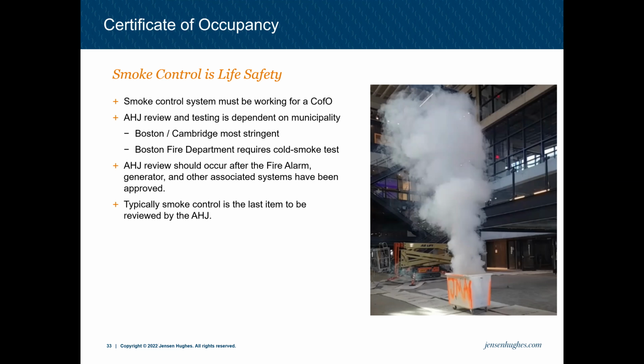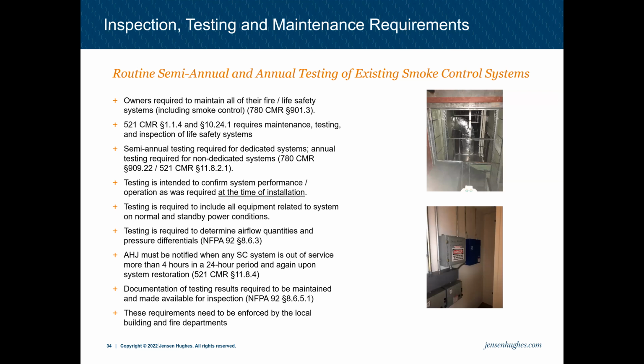So again, as we talked about earlier, look at scheduling, making sure that your NFPA 72 affidavit is done. Then you submit the special inspection report, and the earliest is usually 2 weeks from submission of that report to when BFD would come out to test the system. And that can be difficult in a project where the last couple of weeks get very condensed. So that's generally all we're going to talk about during a typical design project that goes from programming through construction.